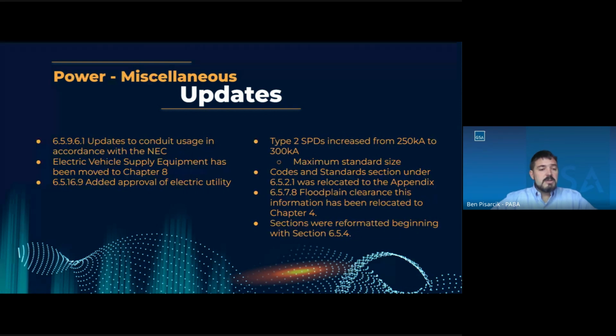The electric vehicle supply equipment was moved to Chapter 8, which we're going to talk about a little bit later. We added the approval of the electric utility, and this is under the PV section. It's very important, especially if you're planning the backfeed. Type 2 SPDs increased from 250 kA to 300 kA. That's the maximum standard size, and I think the next size down would be 260, so we moved it up to the maximum standard size.